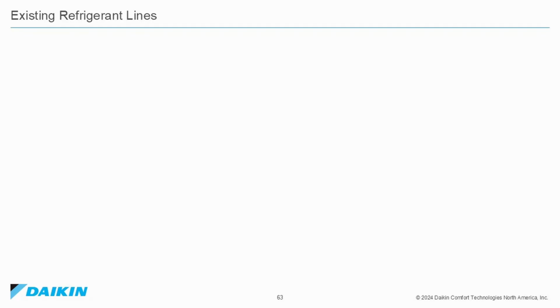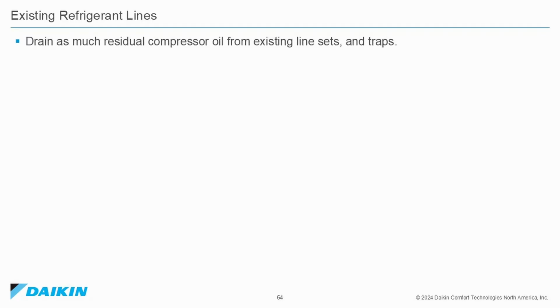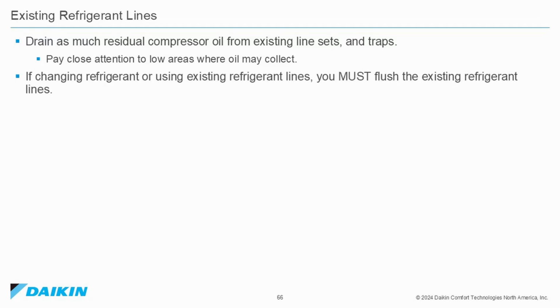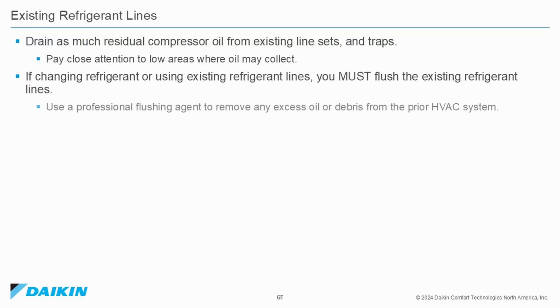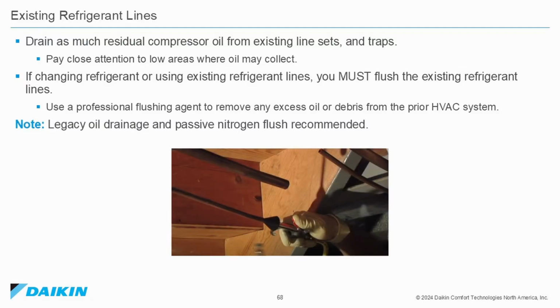Existing refrigerant lines. Drain as much residual compressor oil from existing line sets and traps as possible. Pay close attention to low areas where oil may collect. If changing refrigerant or using existing line sets, you must flush the existing refrigerant lines. Use a professional flushing agent to remove any excess oil or debris left by the prior HVAC system. Legacy oil drainage and passive nitrogen flush recommended.